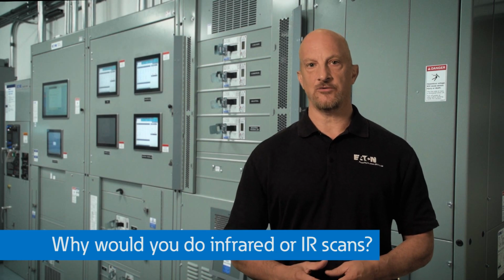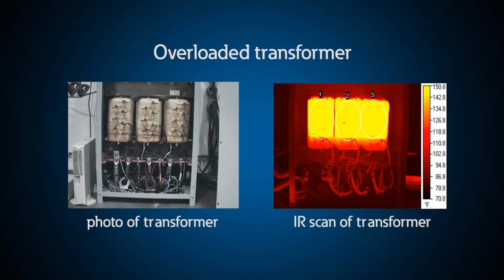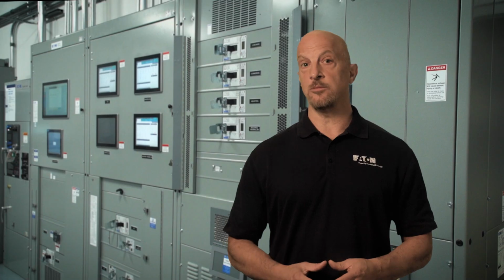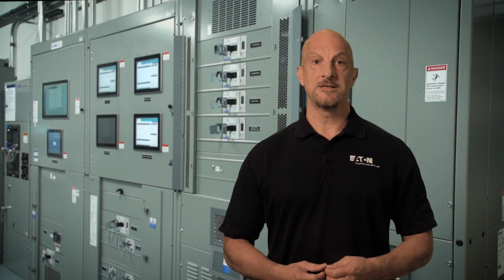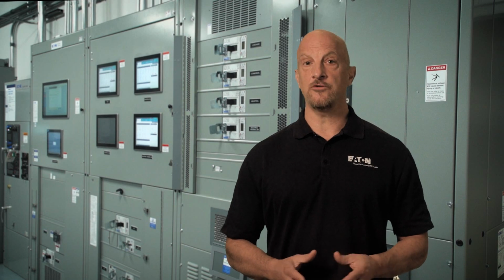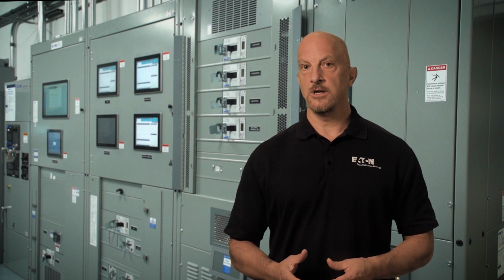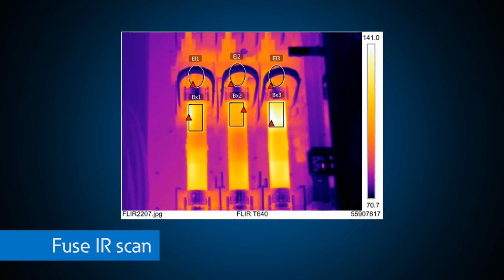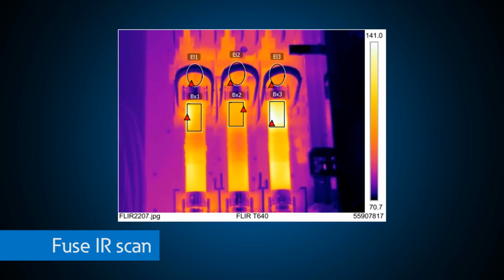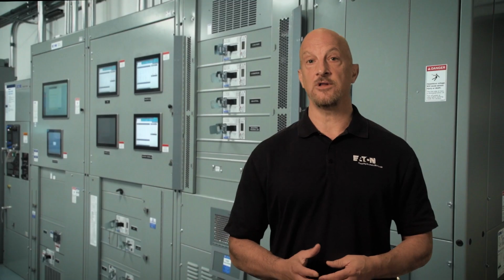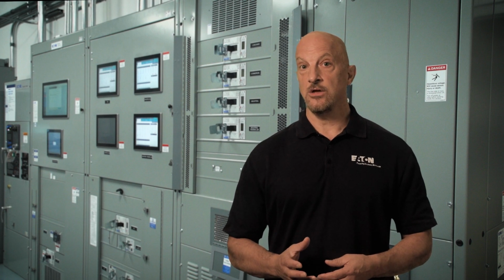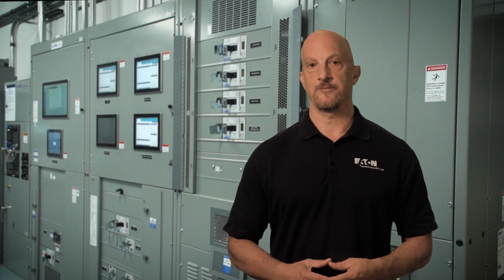Because you can't see electricity and the heat that it creates, we rely on well-proven designs and installation practices to avoid problems within our electrical systems. Still, many times you won't know there's a problem until there's a failure. Yet the problem was fully discoverable well ahead of the failure. A majority of potential causes of electrical failures are stealthy. You often don't see or hear them coming.